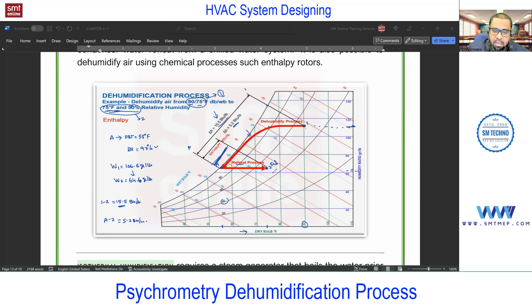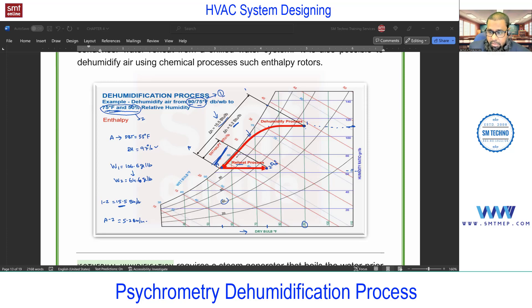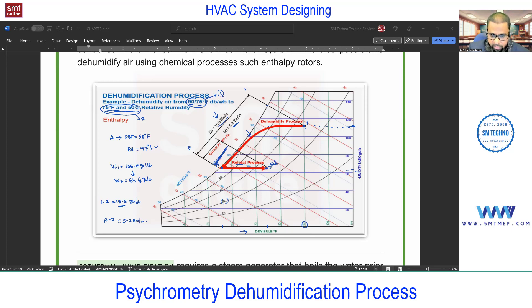So we extract 15.5 BTU per pound then add 5.2 BTU per pound to get the required result. This is the cooling and reheat process for extracting more and more moisture. The dehumidification process involves sensible plus latent cooling — not sensible cooling only. Latent cooling occurs because condensation happens on the evaporator coil. In contrast, evaporative cooling (like an air cooler) involves only sensible cooling without the latent dehumidification process — that case we'll discuss separately.